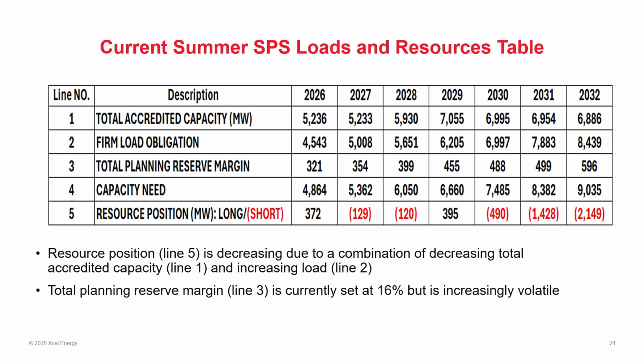Generally, on line one, what we have here is what we call total accredited capacity. Now, accredited capacity does not necessarily mean the same thing as nameplate capacity. As a part of SPP, or Southwest Power Pool's, resource adequacy construct, they determine each resource type's ability to contribute an accredited capacity value. For a natural gas facility, a CT, a combustion turbine, we may see 90% of its nameplate value. So if it's a 100 megawatt unit, we may see 90 megawatts of that unit that can be counted towards meeting our firm load obligation.